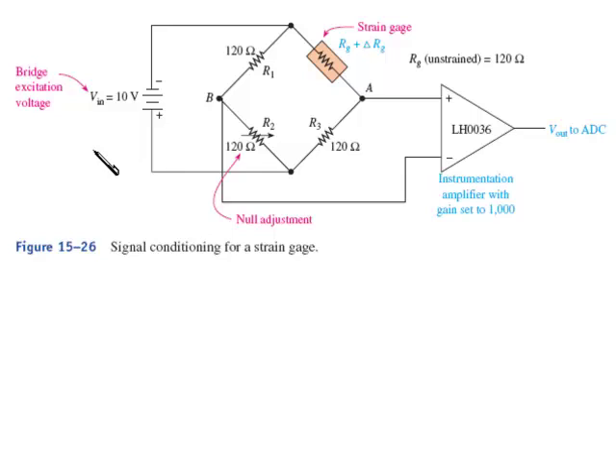This is called a bridge circuit. And we set it up with all 120 ohm resistances. Sometimes we'll actually use four strain gauges because they're all 120 ohms. And put three of them in the non-sensitivity axis and use just one in the sensitivity axis. And that will be this one right here. As you add the weight, this resistance increases in the bridge circuit. You take the small change in voltage that you'll feel at point A relative to point B. You feed it into an instrumentation amplifier with a high gain, and you'll get a high voltage out. This voltage out can be calculated using the following equation.